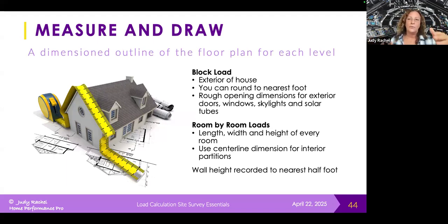That's actually one of the problems with some newer softwares using scanning apps to measure a house—they're measuring the inside of the building. But the procedures tell us the block load uses the exterior measurements of the building. So we want to include the framing member size, and if it's masonry or some other material with thicker walls or a double wall system, we want to include all of that in the load calculation.